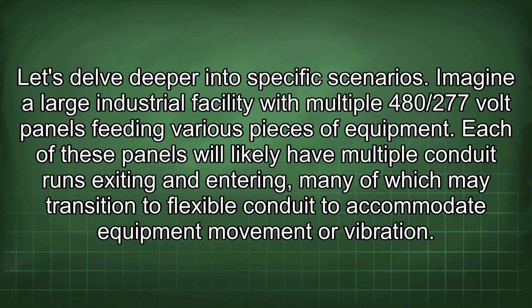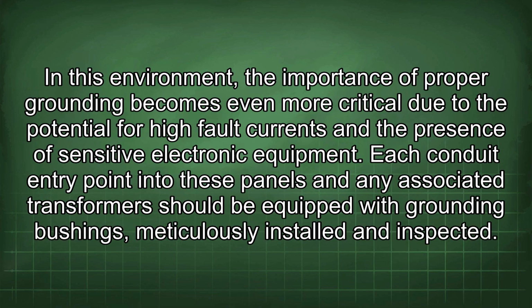Let's delve deeper into specific scenarios. Imagine a large industrial facility with multiple 480/277 volt panels feeding various pieces of equipment. Each of these panels will likely have multiple conduit runs exiting and entering, many of which may transition to flexible conduit to accommodate equipment movement or vibration. In this environment, the importance of proper grounding becomes even more critical due to the potential for high fault currents and the presence of sensitive electronic equipment.